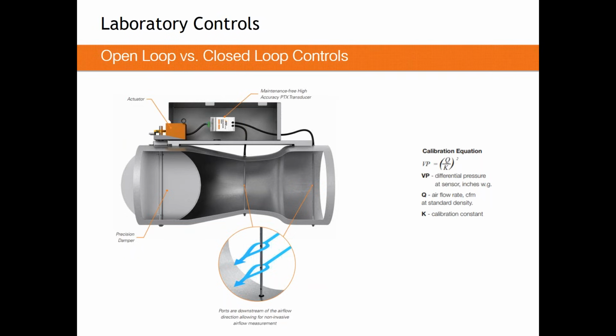For the static pressure, one of the reasons we really like that method of measurement is it brings the pressure measuring posts or orifice, to the back side of the valve, meaning it's out of the airstream. Air is going to flow into the post and around and away from that opening, meaning it's a little less susceptible to contamination. Now, for contamination, anytime you measure airflow, whether it's using velocity pressure or static or vortex shedding or some other method of measurement, no matter how you do it, if you measure airflow, you are susceptible to contamination.